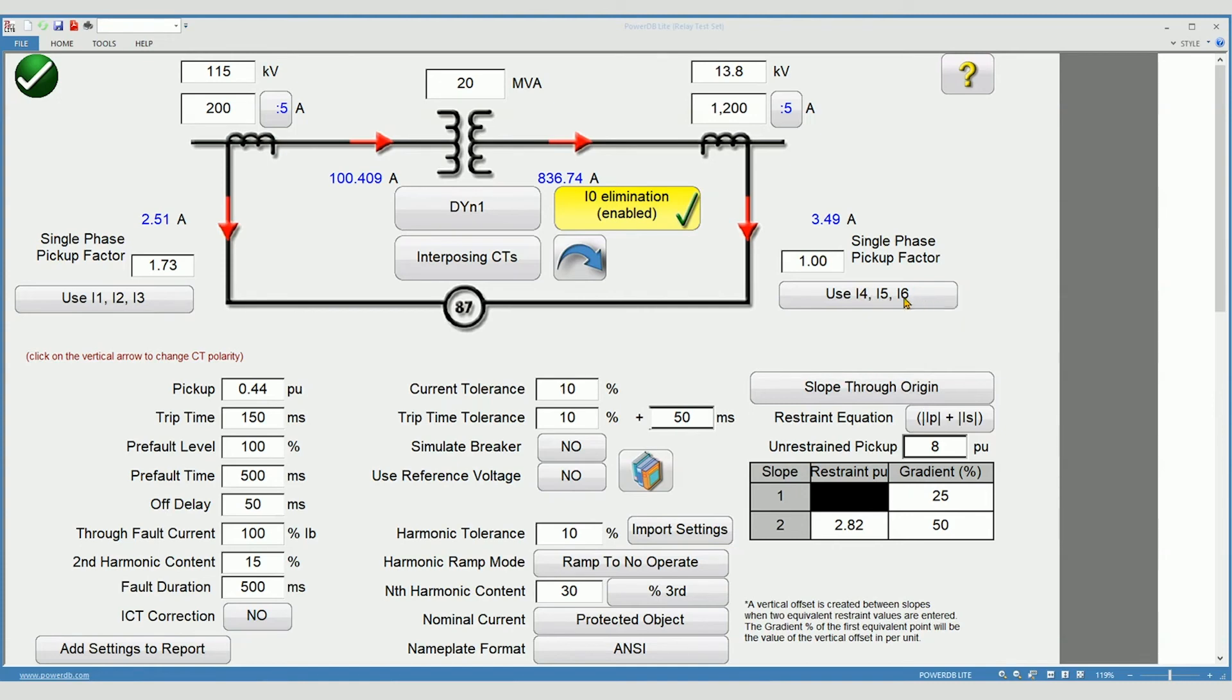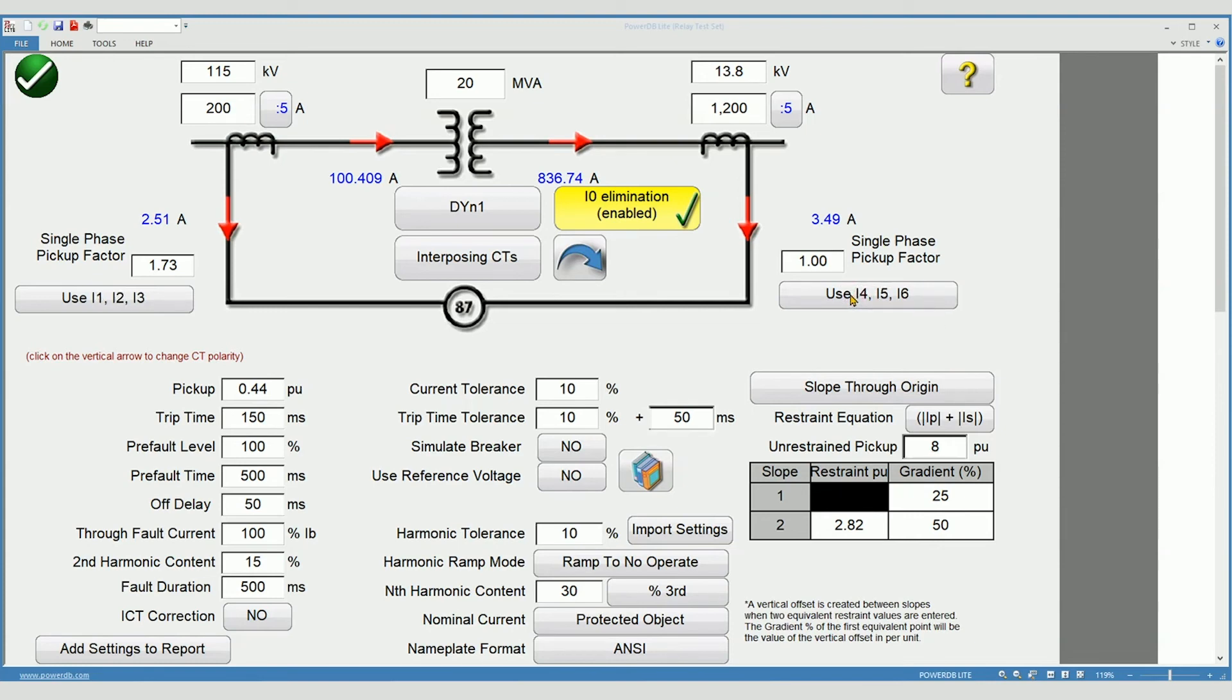Depending on the configuration and the ratios of your transformer and your differential relay, you may need to change where the higher currents are applied.